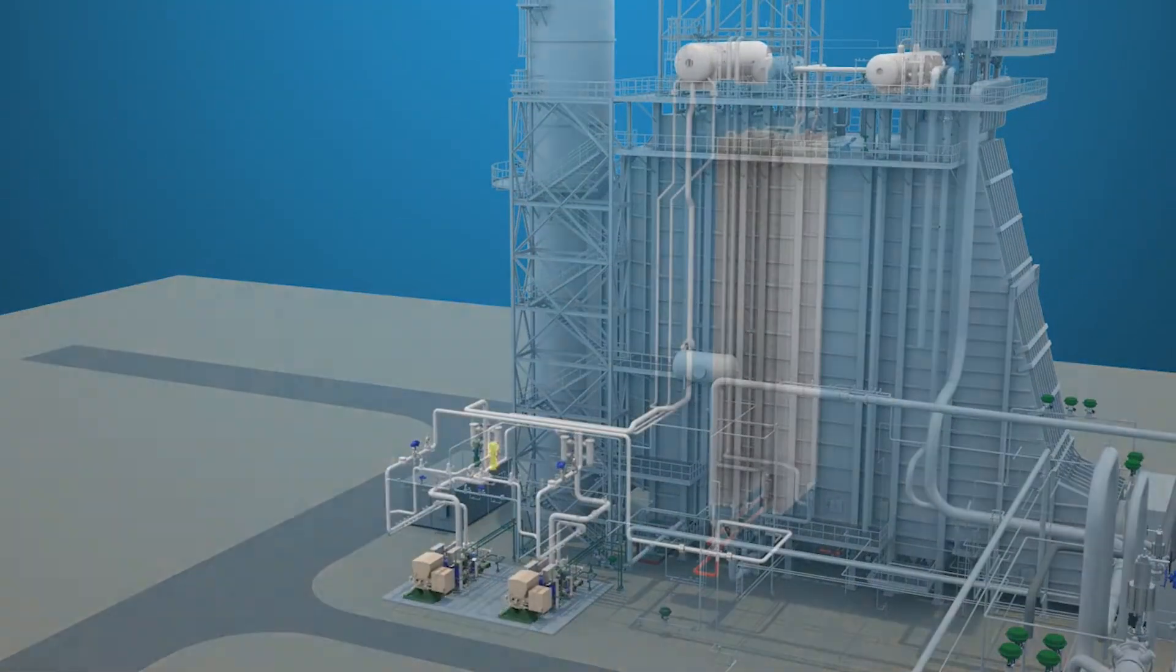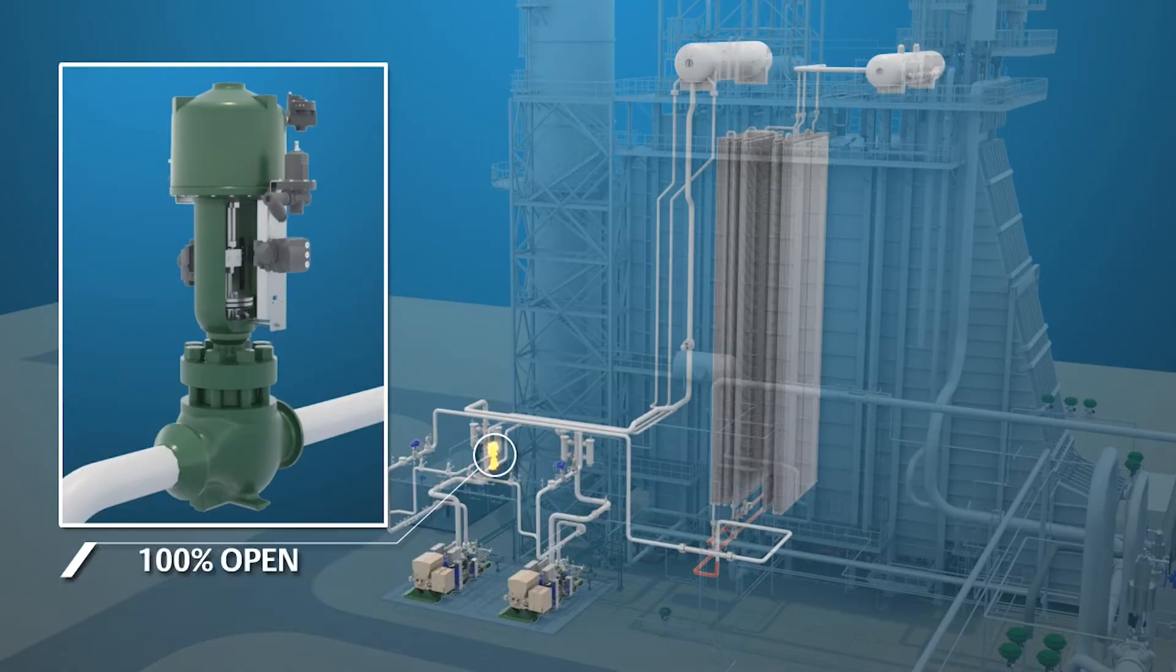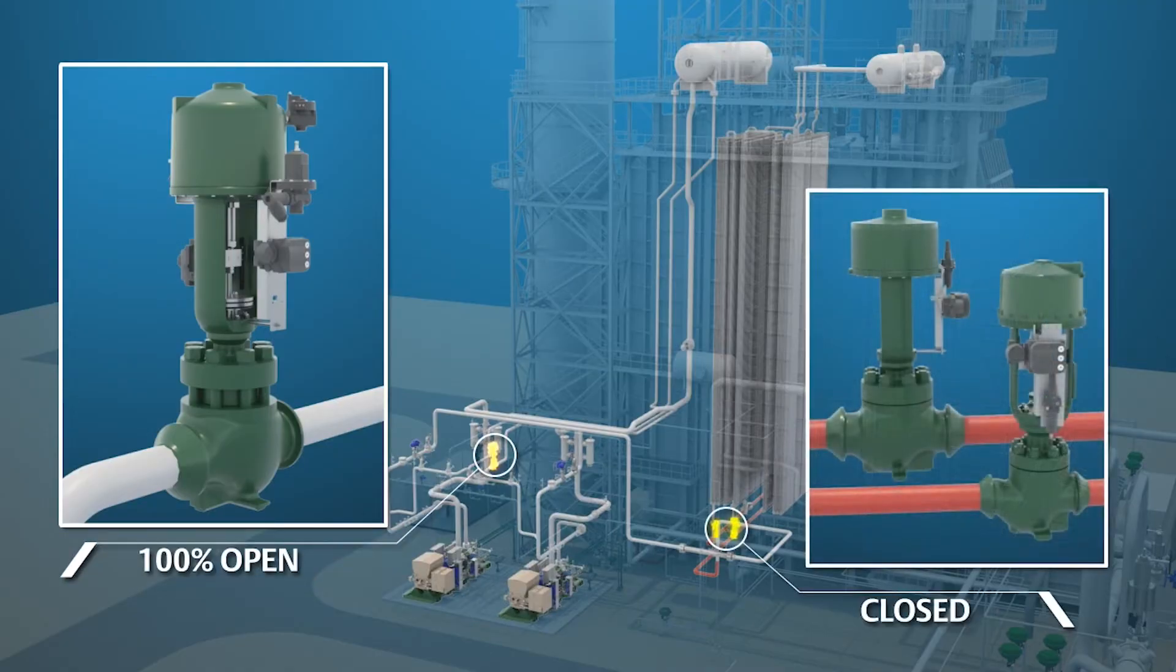To start the pump, the recirculation valve should be 100% open and the downstream feed water regulating valves closed. Once the pump is started, a minimum flow rate as determined by the pump manufacturer will be established through the boiler feed pump recirculation valve to keep the pump cool.